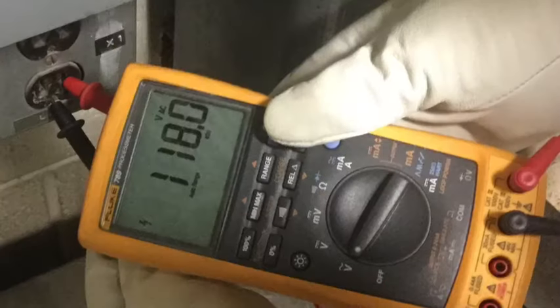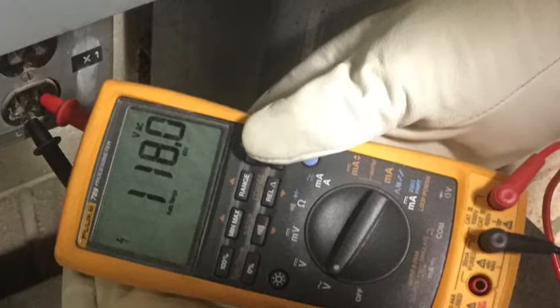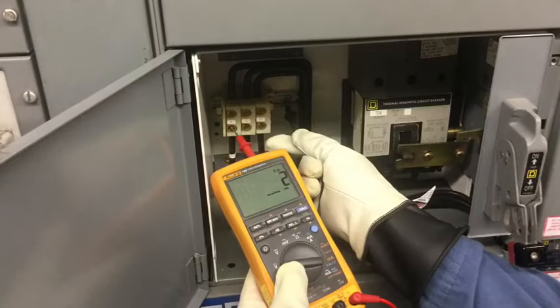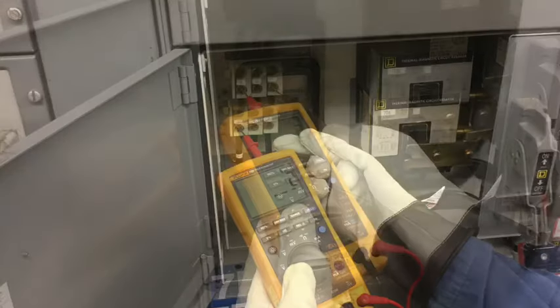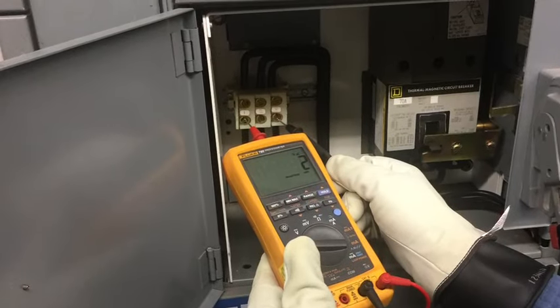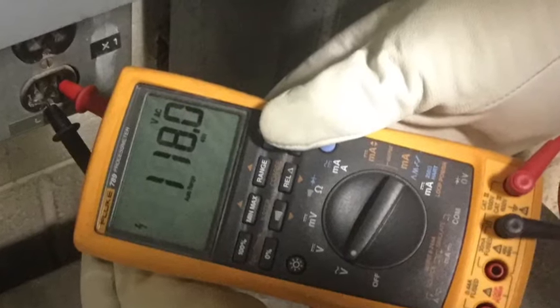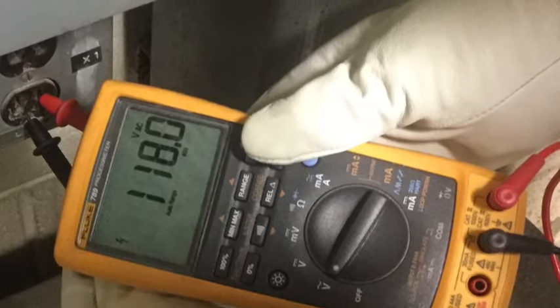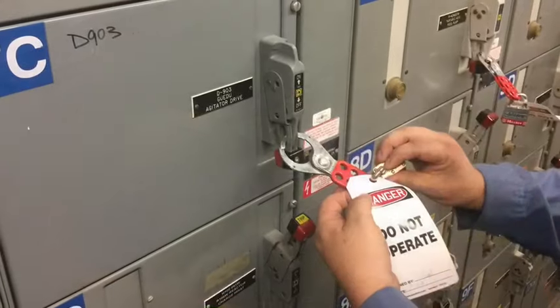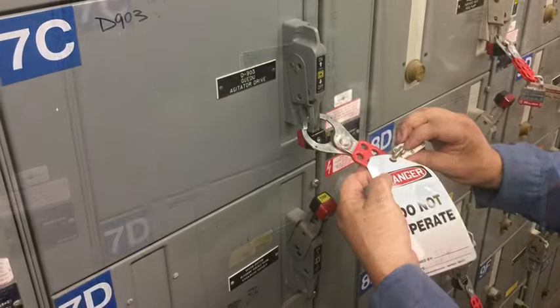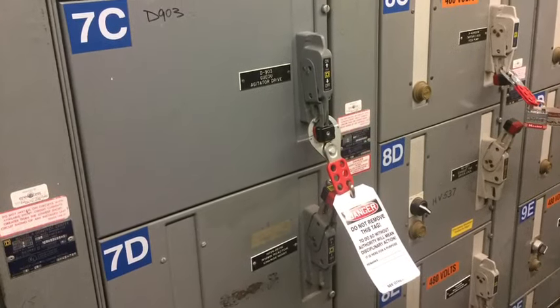It's imperative that you test on known live sources first. Verify the affected equipment as being de-energized. Then test again on a known live source. This will ensure your test equipment is working properly. Finally, using your company's lockout-tagout procedures, secure the voltage source.